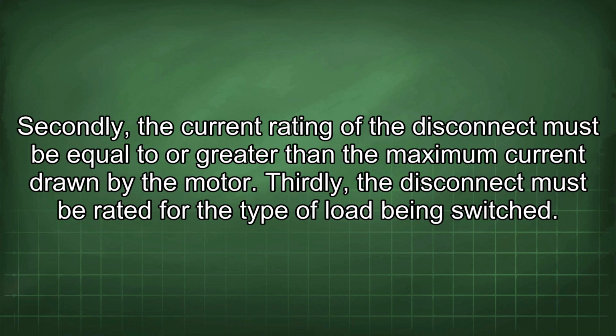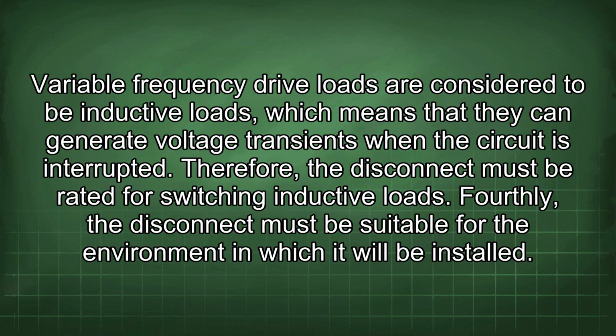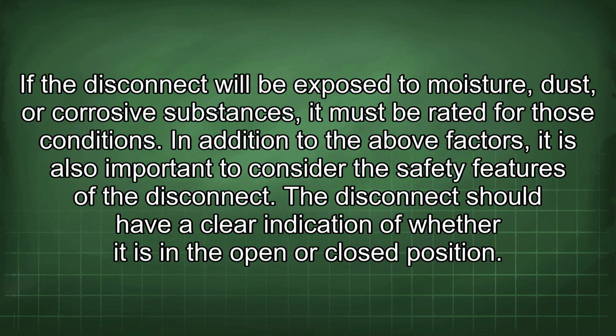Thirdly, the disconnect must be rated for the type of load being switched. Variable frequency drive loads are considered to be inductive loads, which means that they can generate voltage transients when the circuit is interrupted. Therefore, the disconnect must be rated for switching inductive loads. Fourthly, the disconnect must be suitable for the environment in which it will be installed. If the disconnect will be exposed to moisture, dust, or corrosive substances, it must be rated for those conditions.